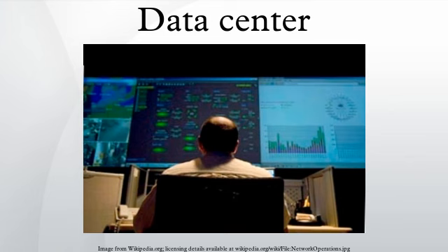Data centers typically have raised flooring made up of 60 cm removable square tiles. The trend is towards 80-100 cm void to cater for better and uniform air distribution. These provide a plenum for air to circulate below the floor, as part of the air conditioning system, as well as providing space for power cabling.